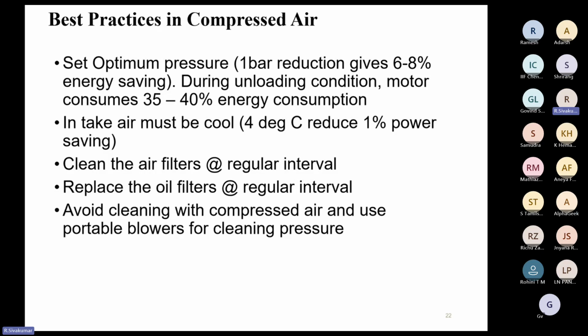During unloading condition, the motor consumes almost 35 to 40% of the energy consumption. Normally, in unloading condition, there is no air output from the air compressor, but the motor still consumes energy. Only in loading condition does the compressor deliver air. So we have to consciously reduce the unloading time. Wherever possible, a VFD can be adopted. If there is more unloading, we can adopt a VFD to reduce the unloading power.